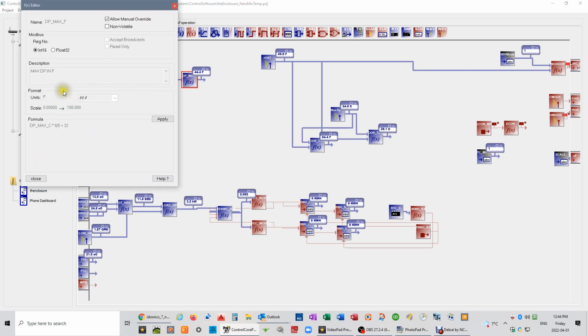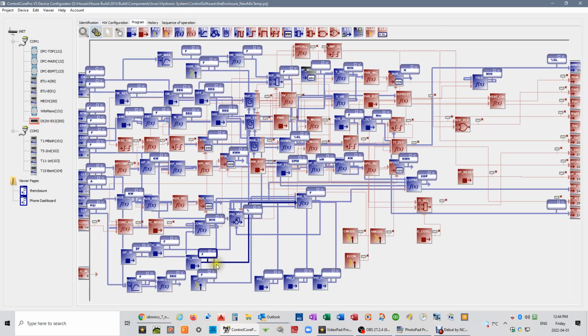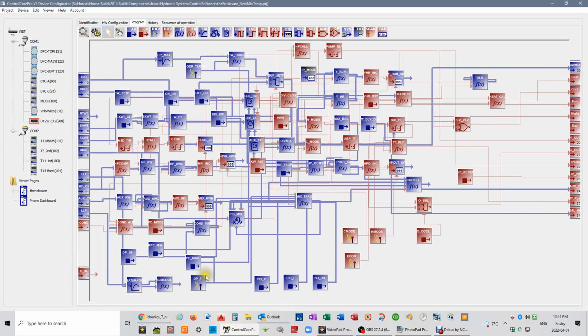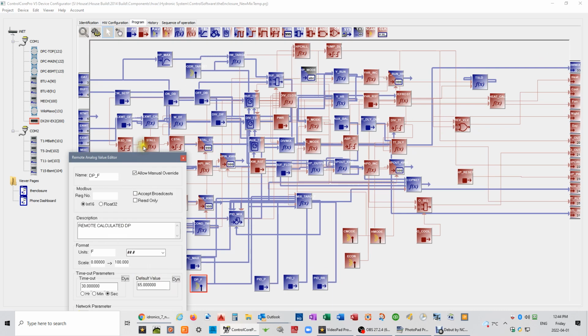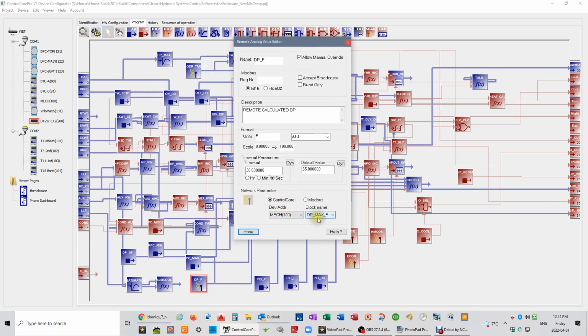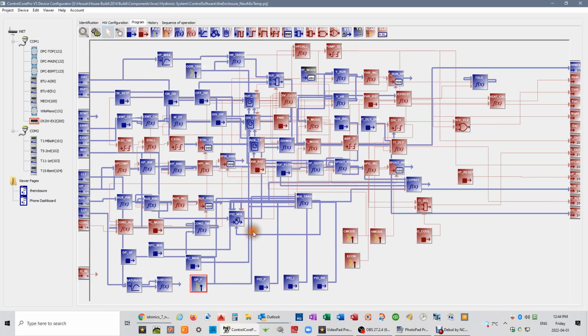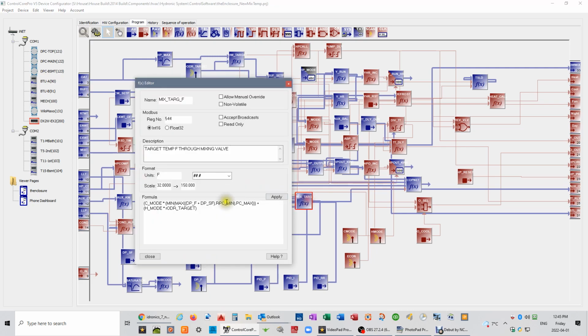So we have max dew point in Fahrenheit. It's called dp max F. And if we go to this block here, let's put this back onto here, it will be calling that remote mechanical iStat dp max F block. So it's remotely calling that, and it is used in the mix target formula for calculating the desired cooling temperature of the system based on the outdoor temperature and the inside temperature's dew point.